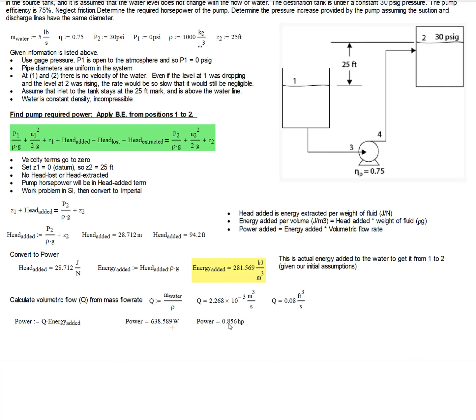Now that's not the final answer though. This is the horsepower required to get this fluid moved from one position to the other. We were told that our pump is only 75% efficient.